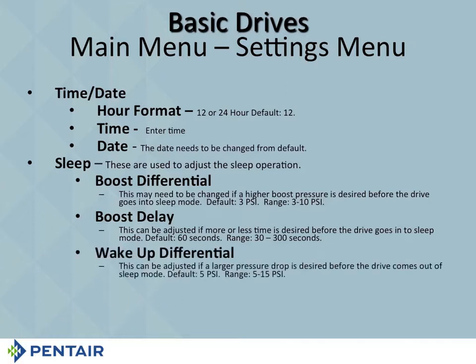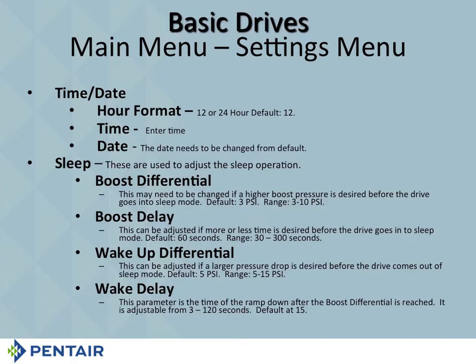Wake up differential, we defaulted it to 5. You can change it from 5 to 15. So if you've got a really large tank here and you want to make sure you're flushing that tank out, you may want to either change the boost differential or change the wake up delay. But remember, whichever you do, your customer is going to notice that pressure differential in there. And then wake up delay, we've set it for 15 seconds. It goes all the way down to 3 or all the way up to 120.